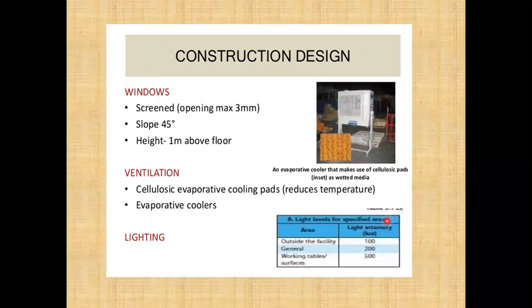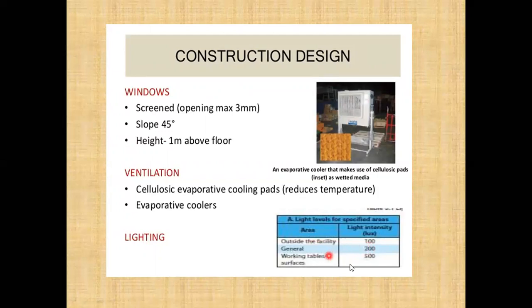Windows should be screened with a 45-degree slope at a height of 1 meter above the floor. For ventilation, evaporative cooling pads can be preferred. Lighting should be provided at approximately 100 lux outside the facility, 200 lux for general areas, and 500 lux on working table surfaces.